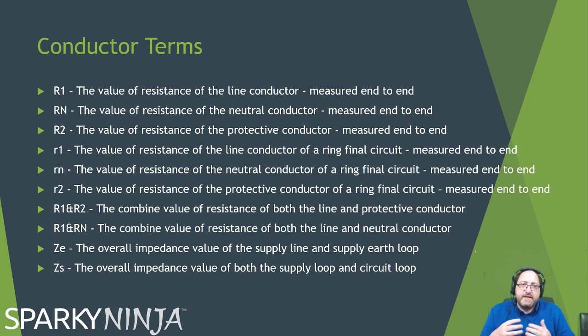ZE and ZS, these are, again, R is resistance, which is done on a de-energized circuit. Z is impedance, which is a measurement of resistance, but on an energized circuit. So they're both resistive measurements. They're both measured in ohms. It's just one is resistance and one is impedance.